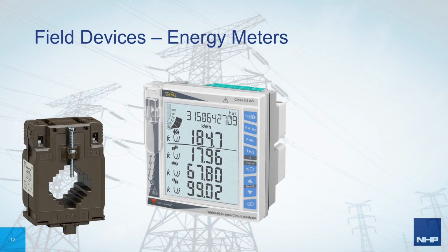The next device to consider is the energy meter itself. The energy meter takes in the current signals from the CTs and calculates and displays the actual primary current value. Some energy meters, usually those rated for smaller loads, have built-in CTs that allow a direct connection of the meter to the supply lines. Some energy meters take that 333 millivolt signal from a current transducer and can make for a very fast installation, as quick connect plugs are often used with these types of CT/meter combinations.